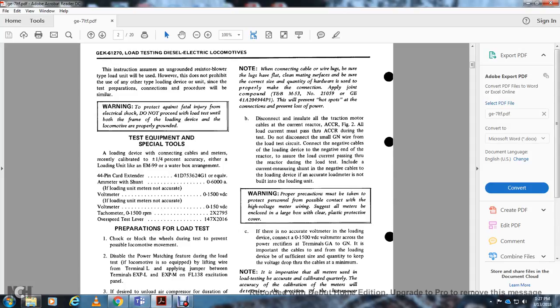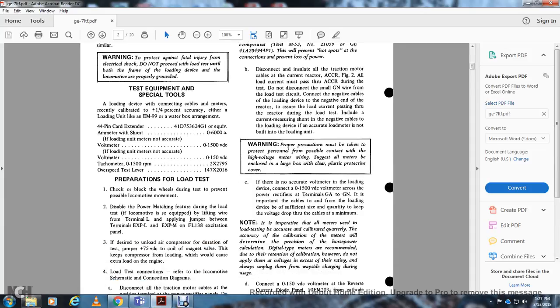Include a current-measuring shunt in the negative cable to the loading device and an accurate load meter, not built into the loading unit. Warning: proper precautions must be taken to protect personnel from possible contact with high voltage meter wiring. Suggest all meters be enclosed in a large box with a clear plastic protective cover.